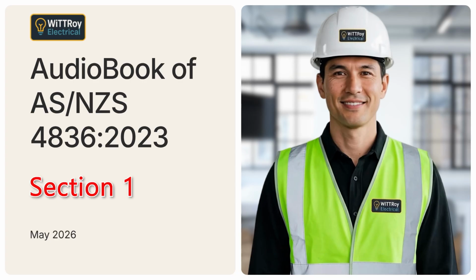Clause 1.4.18. Electrically safe work condition. An electrically safe work condition is a state where a conductor or circuit part has been isolated from energized parts, locked or tagged as required, tested to confirm there is no voltage, and temporarily earthed if that is needed for personal protection. In simple terms, it is the safe condition we want before work starts.